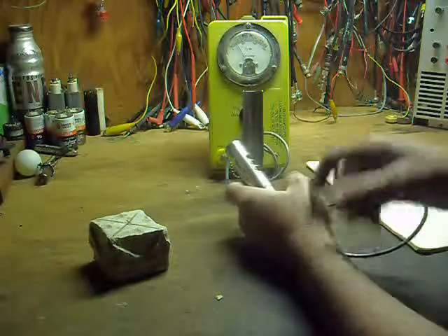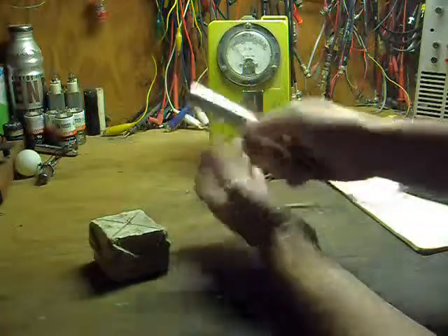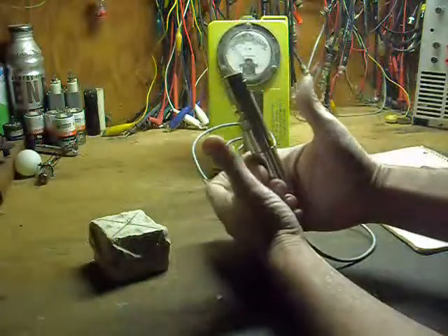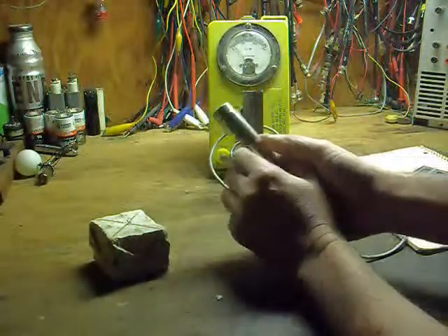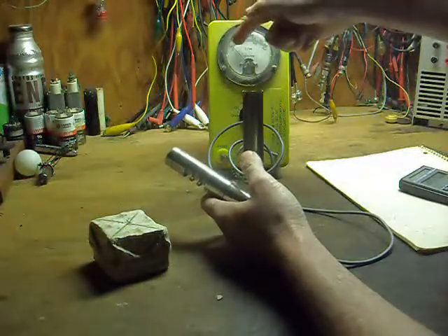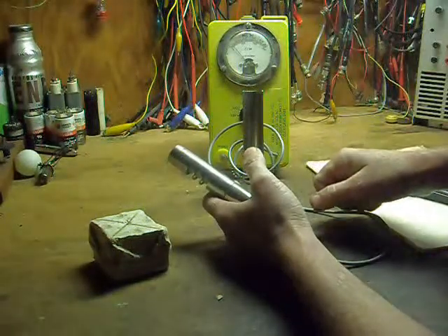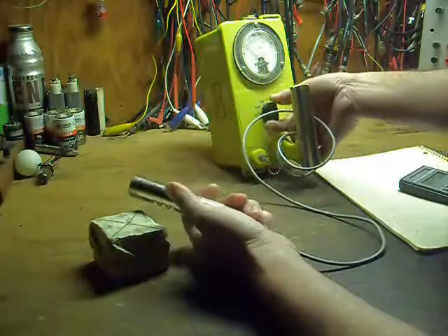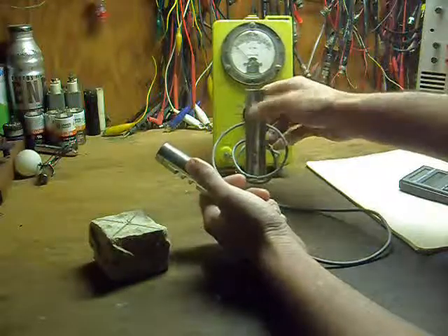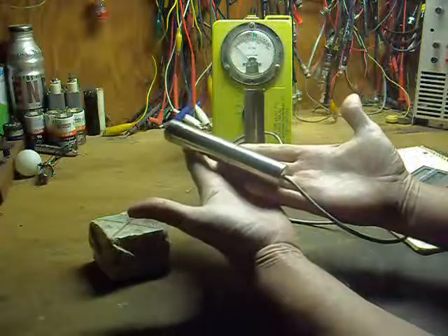In this video, I'll cover what its functionality actually is, what its reading actually means, and how to use it properly. A primary overview of the Geiger counter. You have the meter that has two scales, millirems per hour and clicks per minute. You have a switch that allows you to select a multiplier for the meter above or turn the device off. And finally, you have a radiation detection probe.